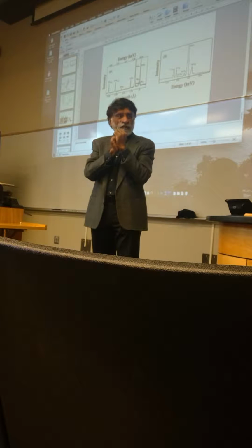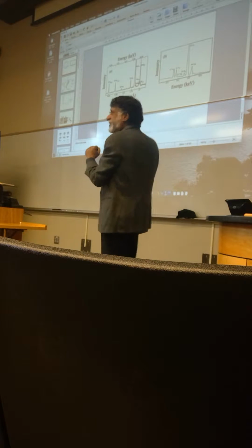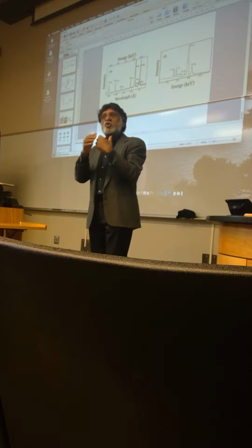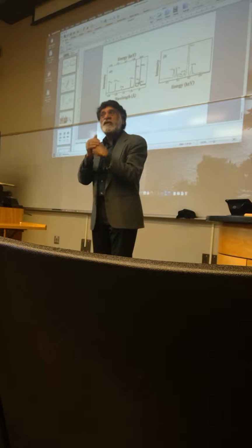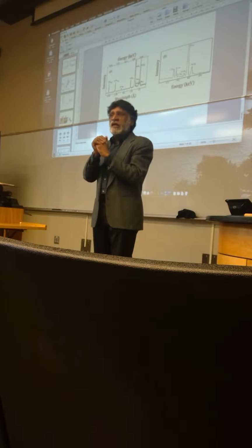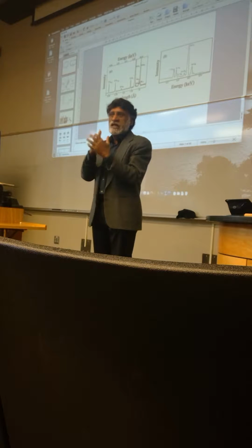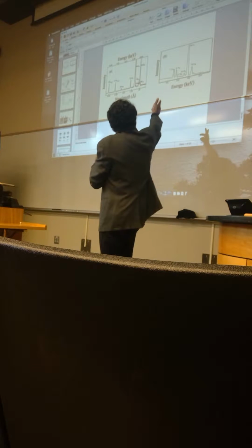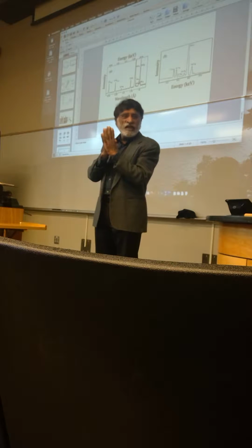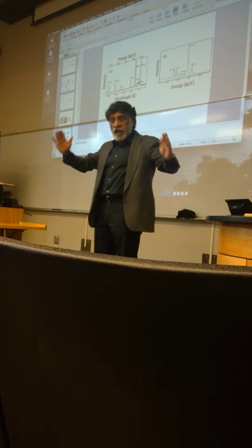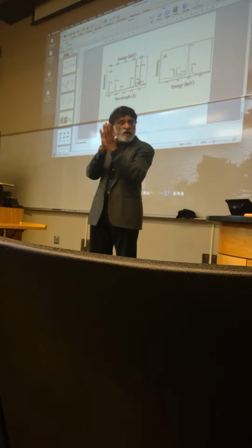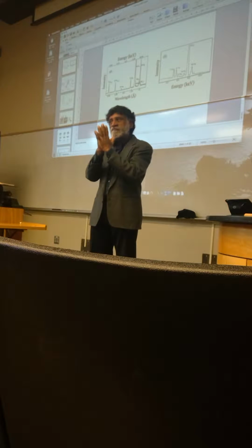the spectrum. On the other hand, if you look at the energy dispersive detector, you look at the energy of the photons that come through, and you use a silicon detector or a semiconductor detector. The simplest one is called a SiLi, or a lithium drifted silicon detector, and that detector gives you roughly about 140 eV resolution. So the peaks are quite wide, whereas here it's about 5 eV. So you can see the peaks are much narrower in the wavelength dispersive case.